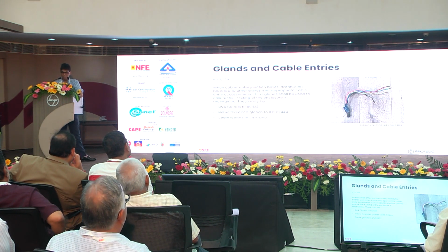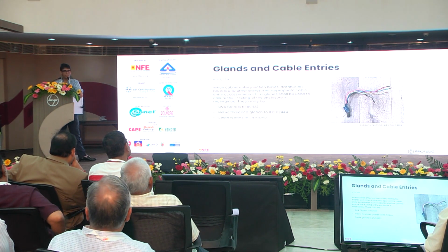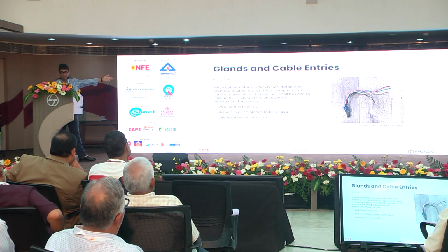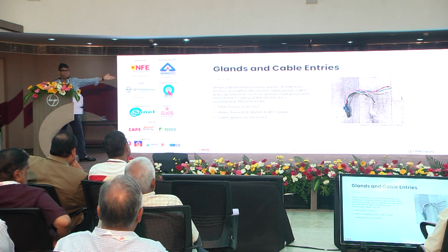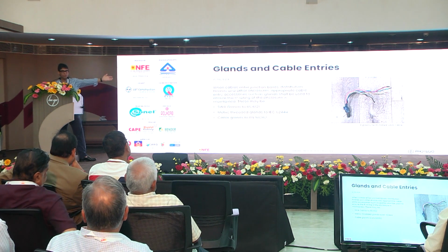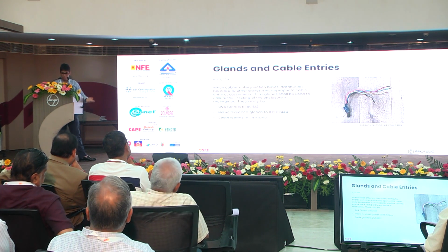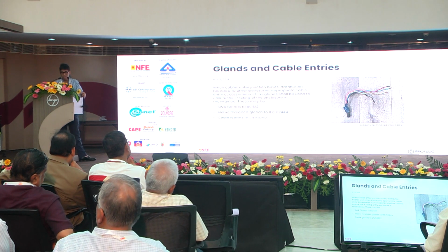Cable entries, there was a gentleman that asked, have any of you all seen this tape joint on armored cable? Pathetic. This was in my own office. Before I got possession of the building, this was the gland. Needless to say, I replaced it with a proper gland.